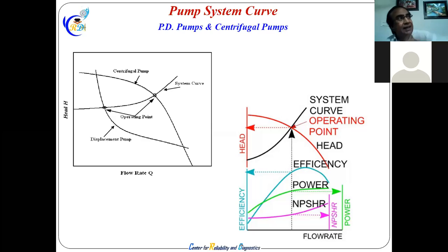If somebody is taking more height, it will not pump more. So things are there. P.D. pumps and centrifugal pumps, different pump selections, and head and flow matter. And these two pumps have to encounter the system curve. Now, depending on the system curves, the flow requirement and the whole head requirement, you can choose which pump to use.